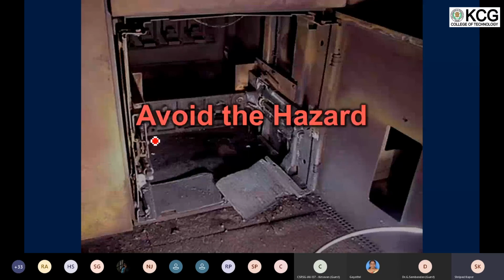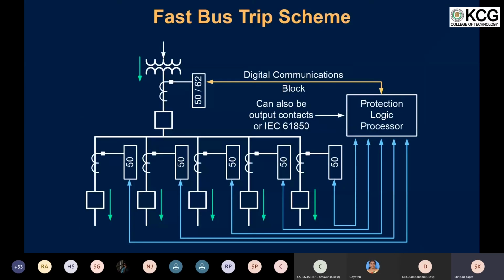So how do we avoid this? What are the steps taken in the industry to mitigate these arc flash hazards? I will be explaining that. Like I mentioned, there is something called a fast bus trip scheme. In the fast bus trip scheme, you send signals from the feeder protection relays on the outgoing feeders to a logic processor, and the logic processor takes care of certain logic. After processing that logic, it may send a signal to the incomer to either trip or not trip.